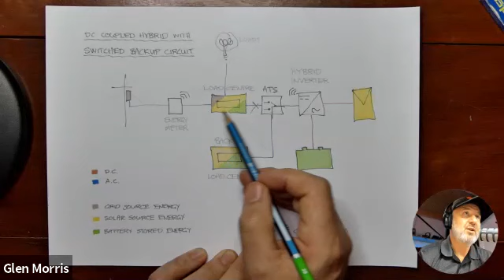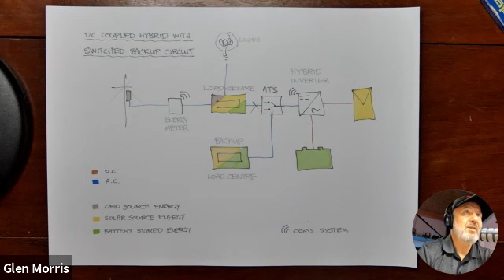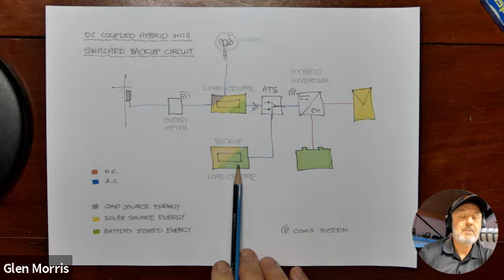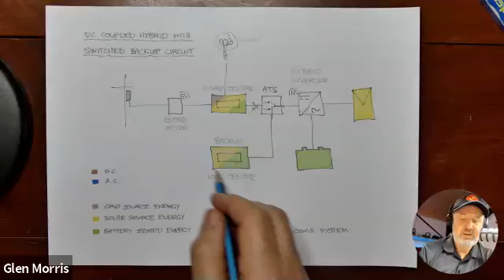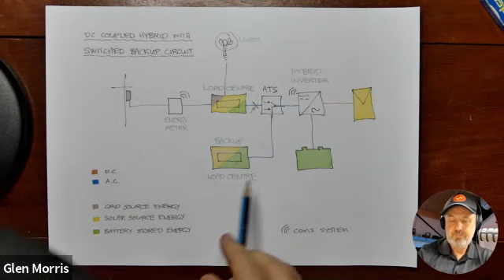The reason for that is the grid goes off for lots of reasons, one of them being a storm where power lines have fallen down, and you don't want to start exporting power out to the street when the power lines are lying on the ground. So it's a safety issue. This achieves that safety by isolating at the connection to the load center, but then you've got a separate backup circuit. This could be a single power outlet, a switchboard, or some dedicated circuits inside the switchboard. I've shown it here as a dedicated switchboard, but it doesn't have to be.